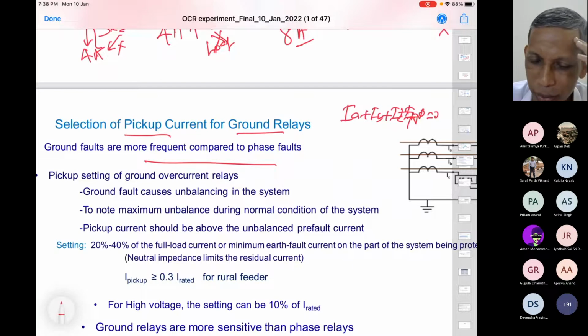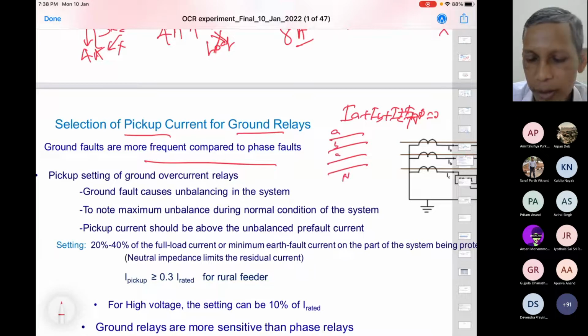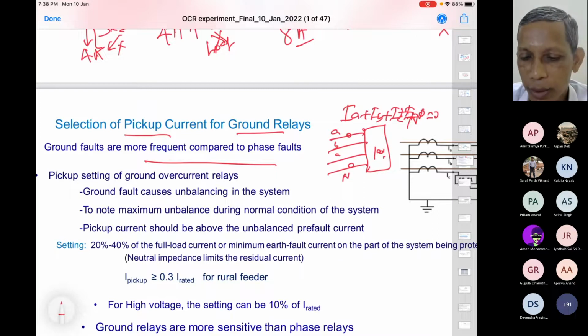Now, when it happens to be ground current, see here, phases A, B, C and N, and this is connected to the load of the system. Even if we have unbalanced load, meaning single phase loads, one load may be connected to one single phase. A small house, 1 kilowatt load, may be connected to only phase A. In my house we have 3 kilowatt or 5 kilowatt load, so there is 3 phase supply. The point here is that when there are a lot of single phase supplies, there will be unbalance. But unbalance means the corresponding neutral current will be there.